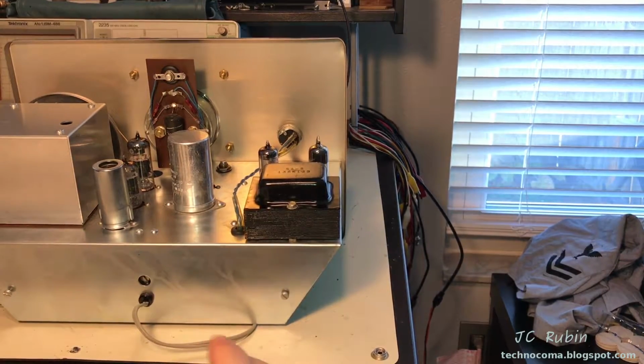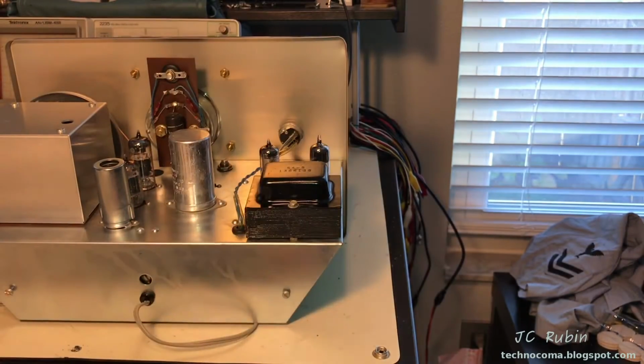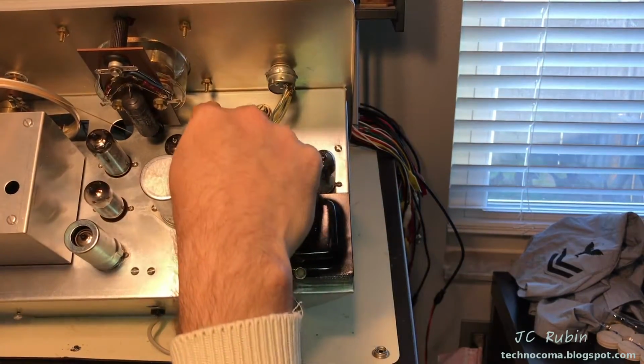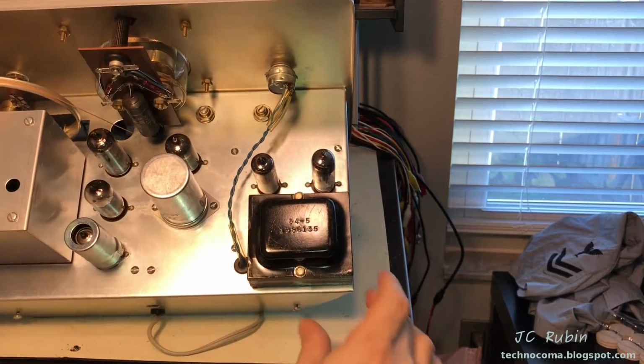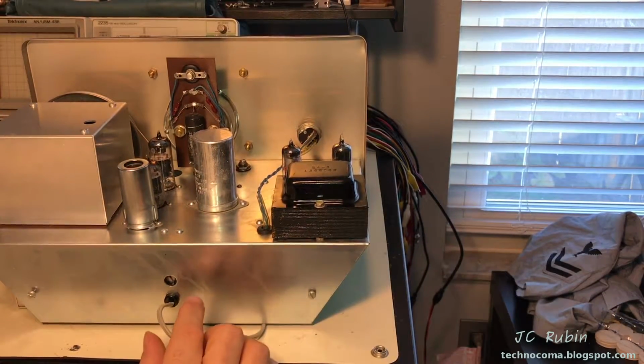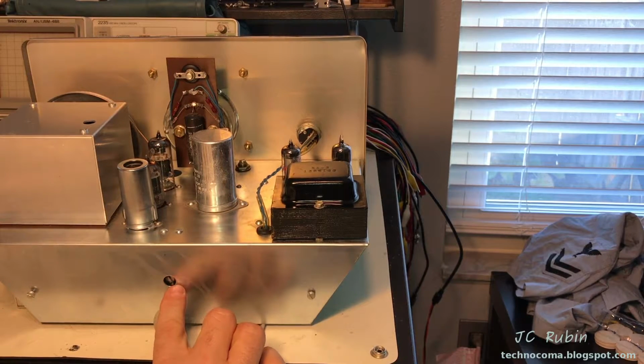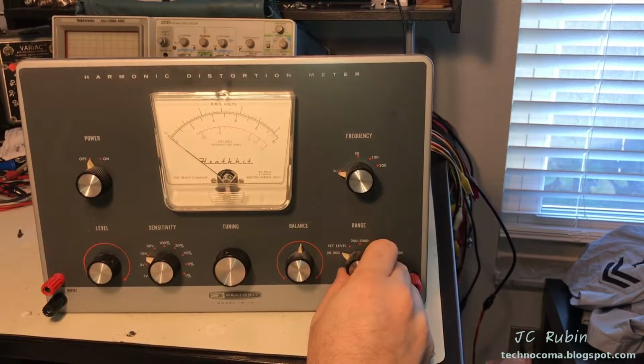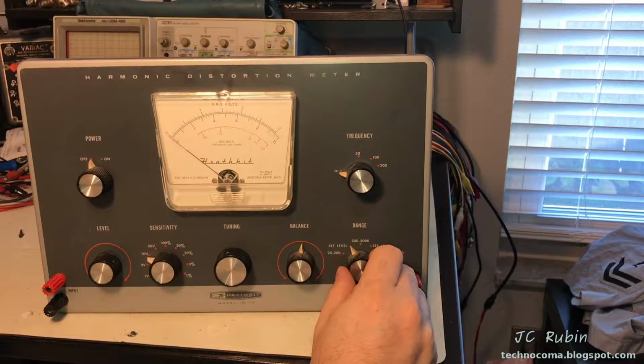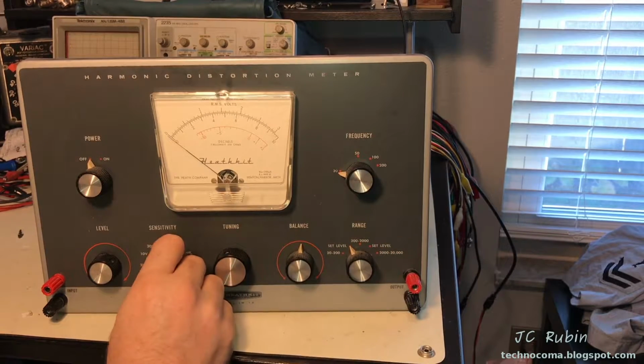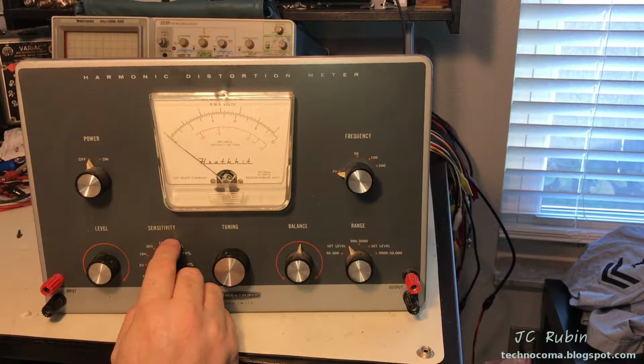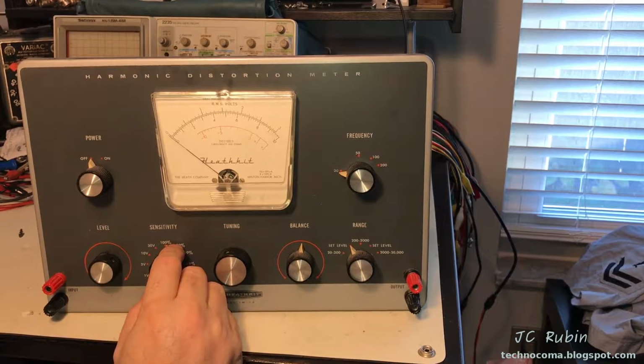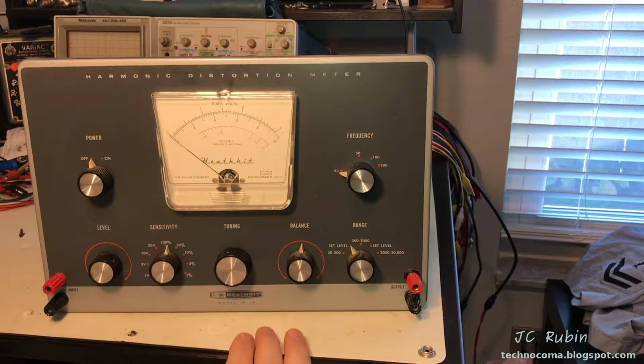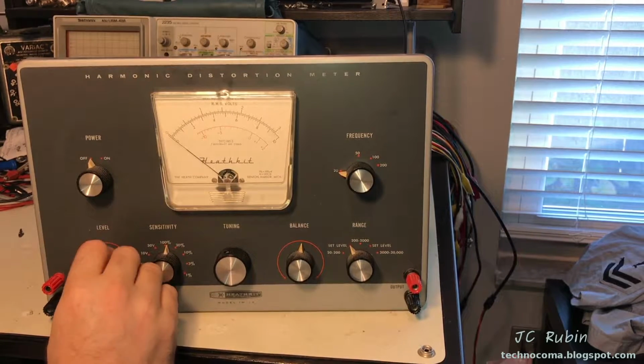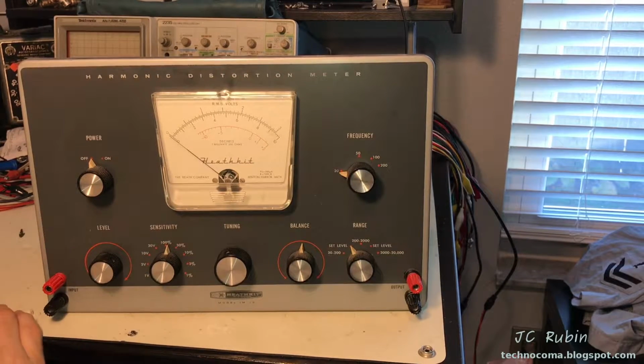The first part of test and calibration has the setting of these two pots here, labeled H and G, to the middle position, and there's a pot over here, F, that is to be set fully counterclockwise, so I'm going to do that now. With that completed, it says set range switch to set level. I imagine either set level is fine, and set the sensitivity to 100%. And I realize we're doing this without the calibrated resistors, but we're going through the exercise. Set the level control right here fully counterclockwise, as I have done.